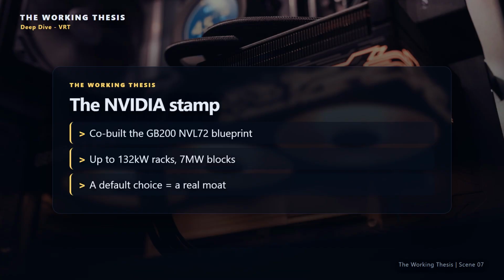Vertiv co-developed an end-to-end power and cooling reference architecture with NVIDIA for the GB200 NVL72 platform, the dense Blackwell systems, designed for racks up to 132 kilowatts and scalable to 7 megawatt data center blocks. Why does that matter so much? Because when NVIDIA effectively publishes a blueprint that says here's how to power and cool our flagship AI system, and Vertiv's gear is in that blueprint, Vertiv becomes a default choice for anyone deploying it. It's a hybrid liquid and air design, built to minimize wasted stranded power and to deploy fast, and speed, when AI capacity is supply constrained, is its own competitive edge.